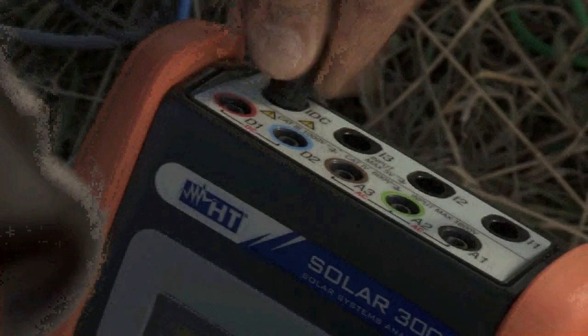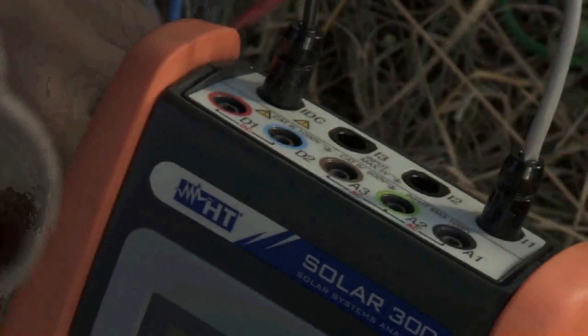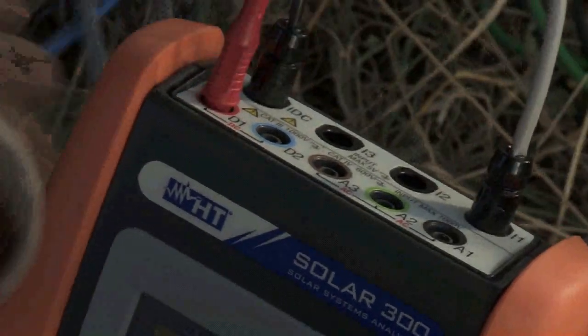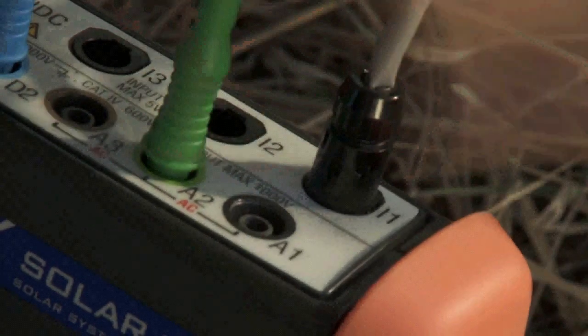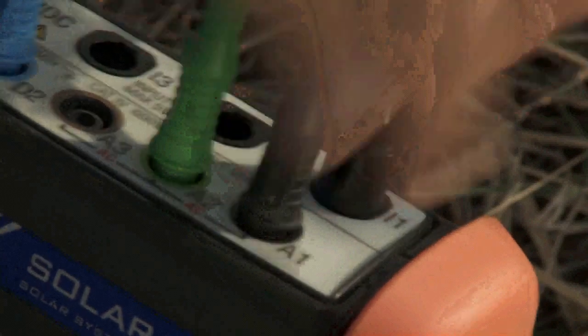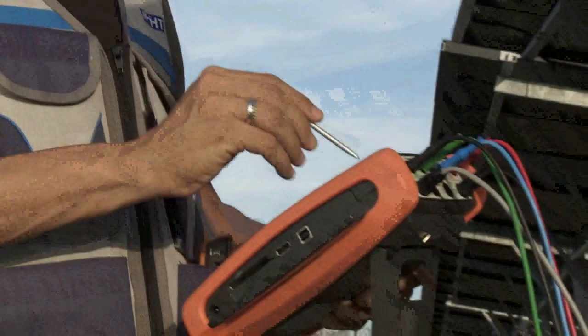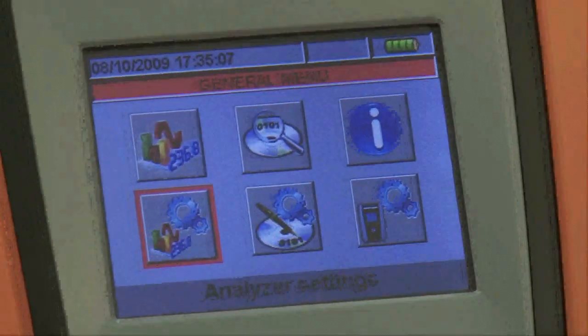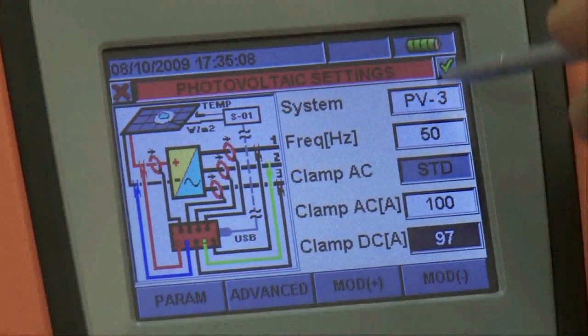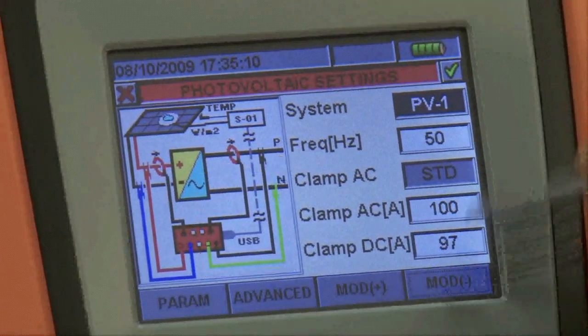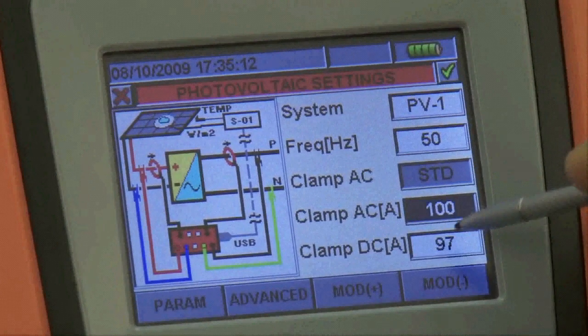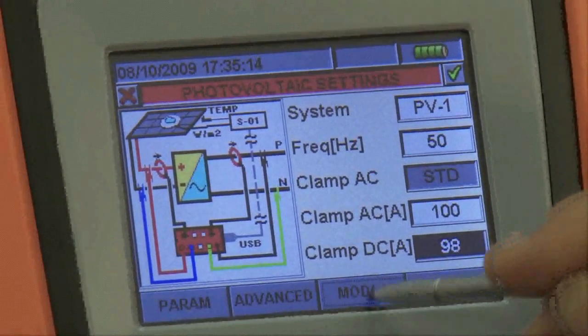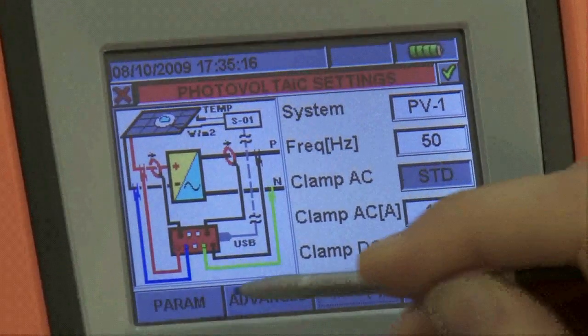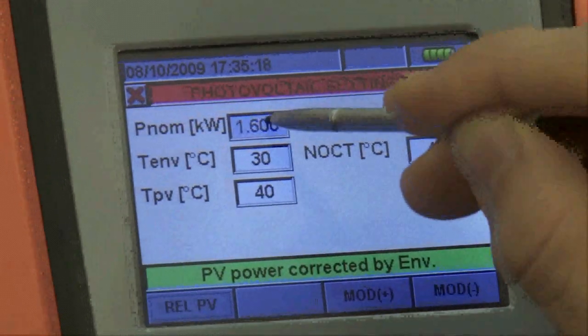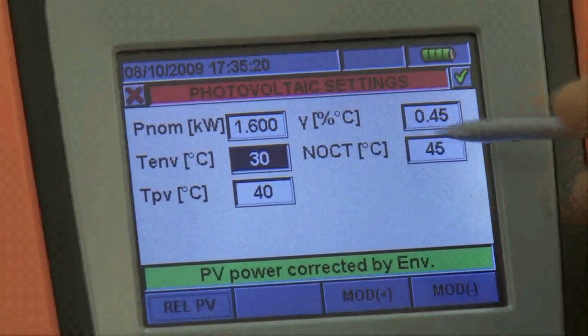Once the voltmetric and amperometric transducers have been connected to the system, you may connect the relevant connectors to the instrument inputs, respecting the colors and abbreviations indicated. The touchscreen makes verifying the settings of SOLAR300N extremely rapid and intuitive. The verifier must set the type of electric system, single-phase or three-phase, the system frequency, the full scale selected for AC and DC amperometric transducers, and finally the parameters of the system tested, including the rated power of the string, the reduction coefficient of power with temperature, and the NOCT of the photovoltaic modules.